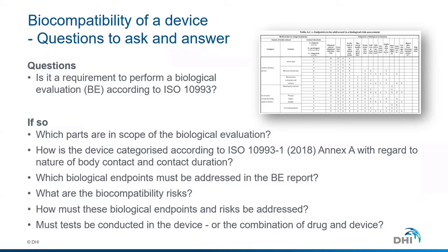That includes sterilization of those components that are used for the device, or if you take only a sample of the device, or a material from the device, then you should make sure and describe how that is valid compared to the device that you actually place on the market. And in some circumstances, it may be worthwhile considering if you need to test both the drug and the device as a combined product, or only the device part in itself.